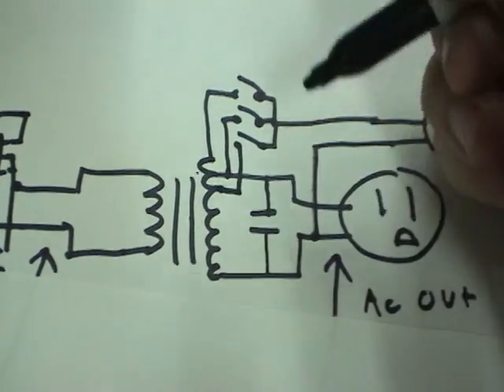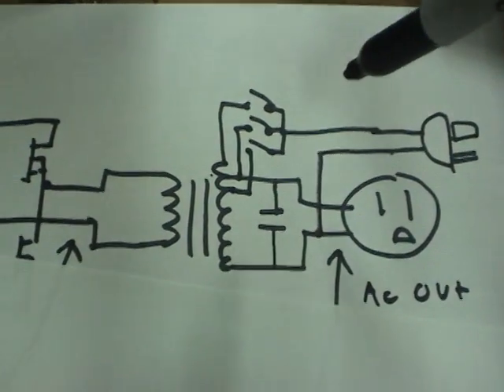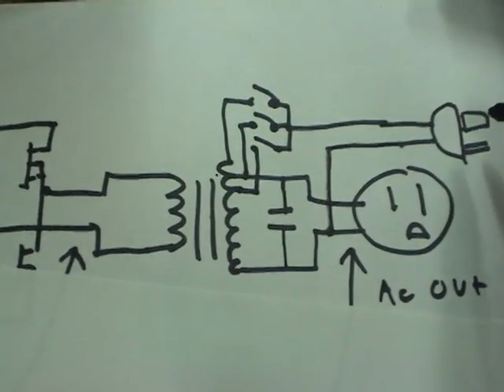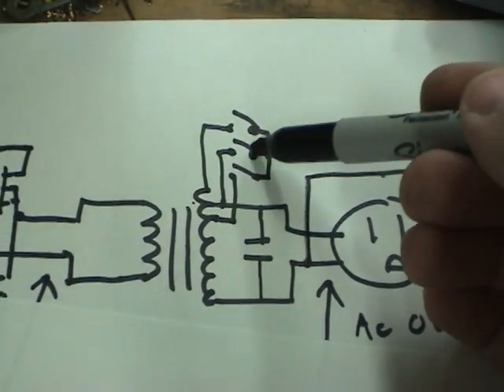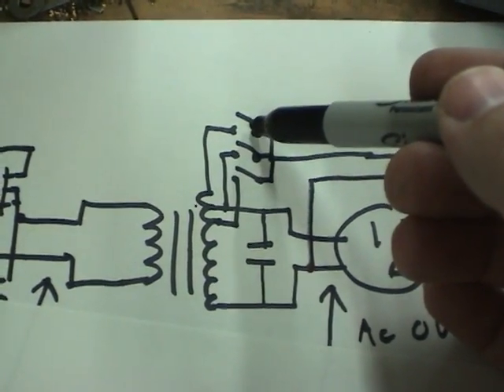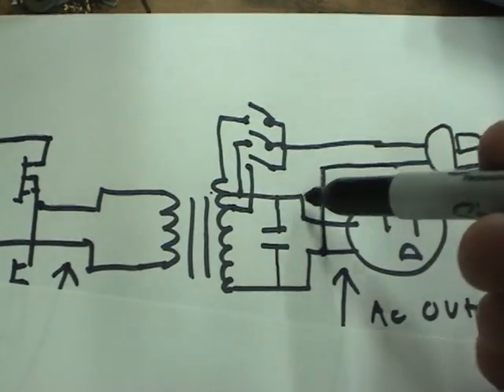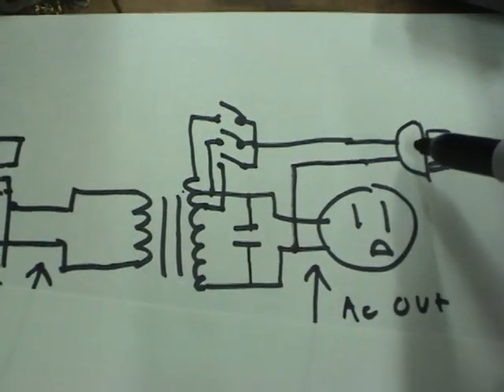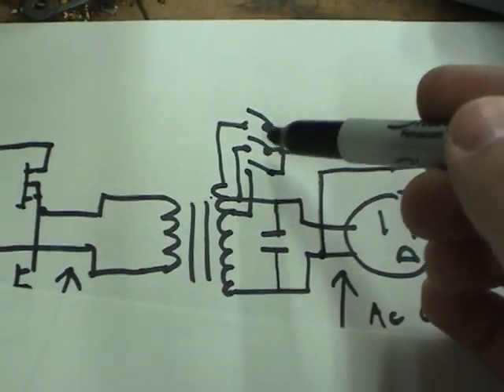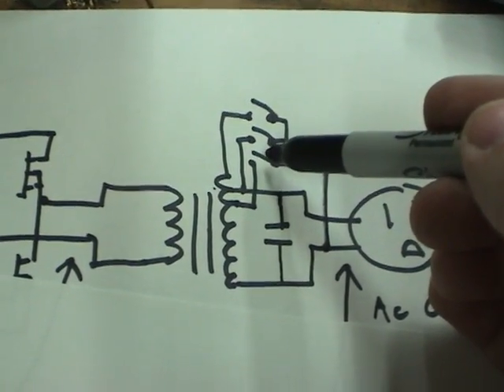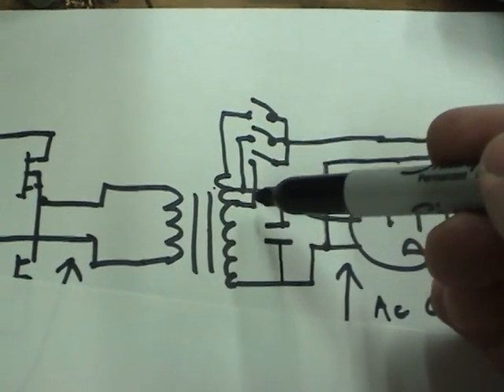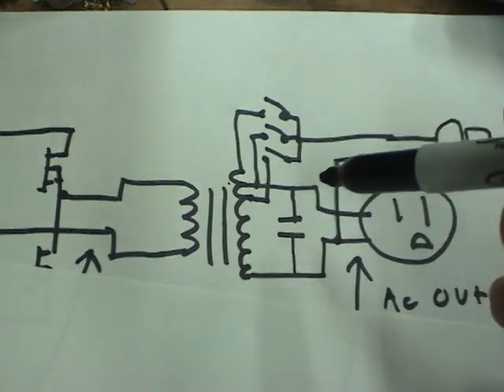And the reason they do that, is so that they can compensate for line voltage variations. So if the line voltage is too high, they'll switch off this relay, switch on this one, which will form an auto transformer, slightly dropping the voltage. And likewise, if the voltage is too low, they'll switch off that one, switch on this one, which will create an auto transformer that slightly raises the voltage.